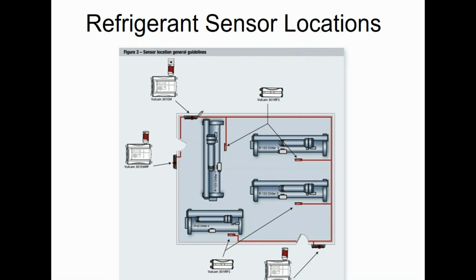Additionally, we have to have some kind of visual and audible alarm inside the room and then outside each door to the room. So in this case, I have 2 entrances, so I need to buy 3 alarming panels for the same system. 1 inside, 2 outside. I could also have 1 main one on the inside and 2 secondary panels that are just feeding off the main one. That would be fine also. But I have to enunciate it outside every door, and I have to enunciate it inside the room. All right.